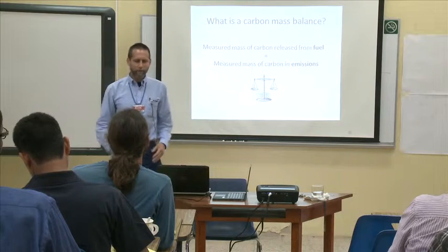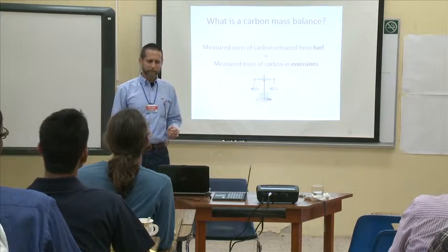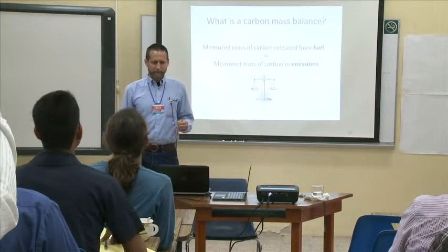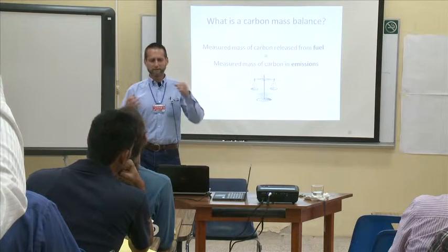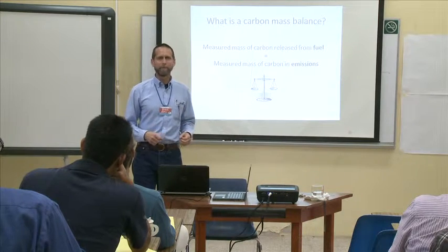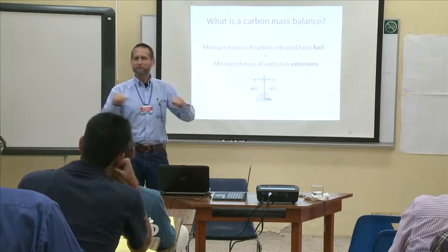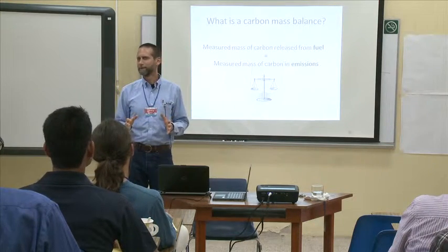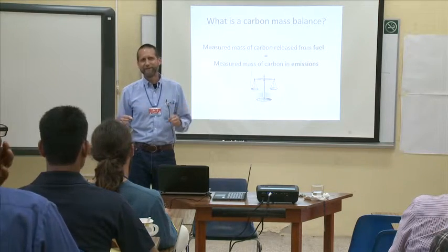First of all, I know that some of you already understand what the carbon mass balance is, but basically the measured mass of the carbon that is in the fuel should be equal to the measured mass of the carbon in the emissions. If that mass balance comes out okay, then you have a really good feeling that what you're doing is right. If it's way off, you know that something is wrong. That's basically it.